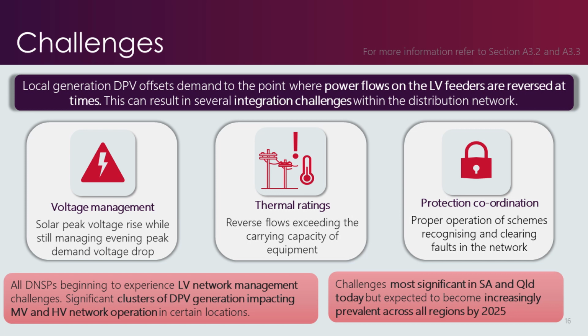Lastly, we have implications for protection schemes within the distribution network. Protection schemes provide a level of security in the event of faults in the distribution network. For example, a car hitting a telegraph pole. These schemes are designed to prevent the impact of the fault spreading too far and potentially damaging more assets, thereby minimizing potential downtime and helping the DNSPs restore the system as soon as possible. DPV introduces flows in the reverse direction, and this can impact the ability of legacy protection mechanisms to discriminate between faults and normal system operation.